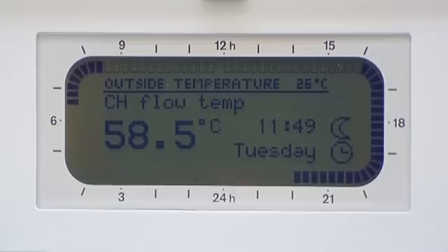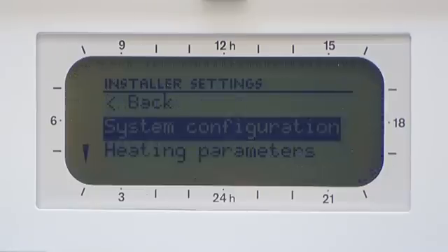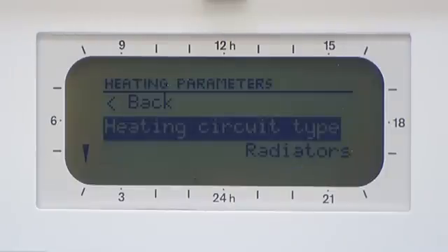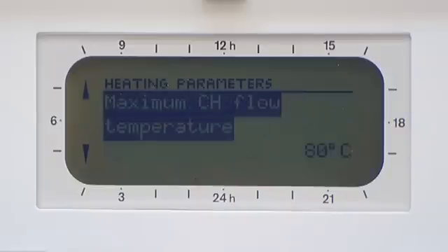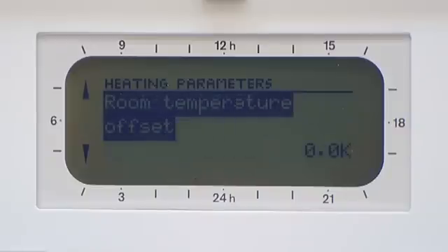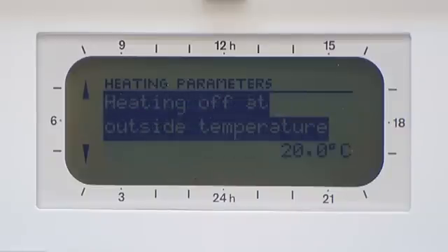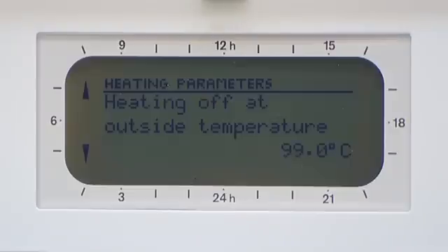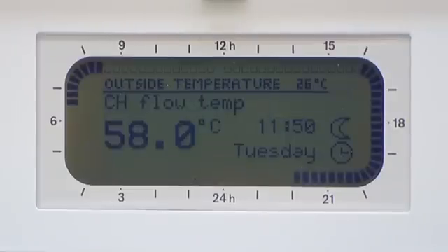Press and hold the menu button for three seconds. Scroll down to heating parameters, press OK. Scroll down to heating off at outside temperatures. Press OK, then using the control knob, increase the value of the temperature to 99 degrees Celsius. Press the menu button to return to the home screen.